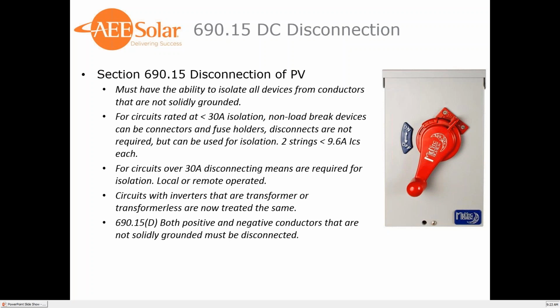Now the less than 30 amps is where it gets a little tricky, I think, because if you do the math backwards from 30 amps and you use 690.8(A)(1), which is our 1.56 multiplier, you're looking at roughly a module with 9.6 amps short circuit current. And that's really probably under the wattage class that we're currently using now. So it's going to be interesting how that actually will work out.